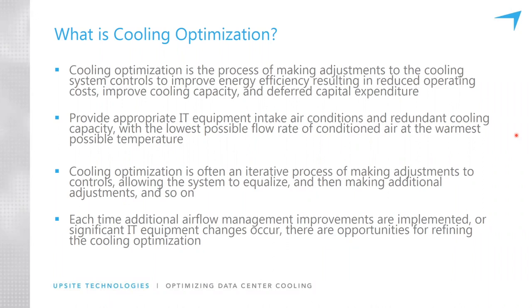Cooling optimization is often an iterative process of making adjustments to the controls, seeing how those affect the environment, letting them equalize and balance, and then making additional adjustments. Also, every time there are significant changes to the airflow management in the room, such as the installation of blanking panels alone, moving some supply tiles around, changes to the IT equipment load or location, some cabinets being decommissioned, or a new row of cabinets being installed and commissioned, then there's an opportunity and a need to make adjustments at the controls level to realize the benefits of those changes, or to make sure that the infrastructure is still matched and tuned to the new conditions in the room.